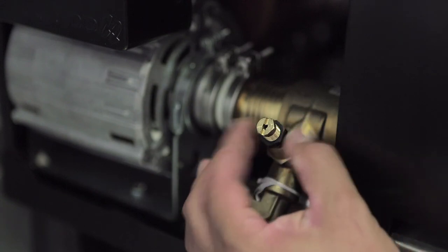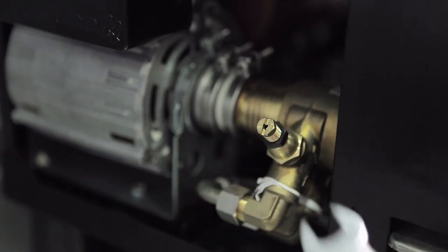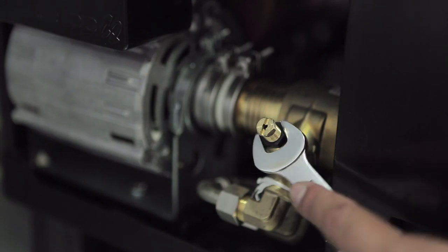Once we have finished the regulation process, we have to make sure we tighten the safety nut so the pressure of the pump does not vary while it's working.